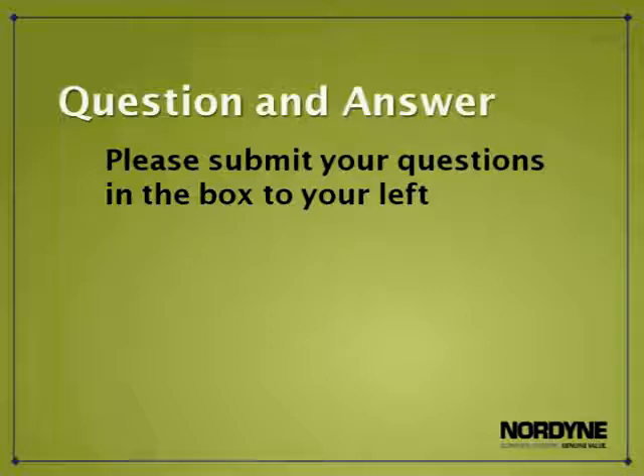Next question from John. What two terminals should be tested to see if the thermostat is sending a call for heat? Really, to test the thermostat, what I would do is put the thermostat into heat mode. Like David mentioned, raise the temperature on the thermostat a few degrees above set point to get a call for heat.